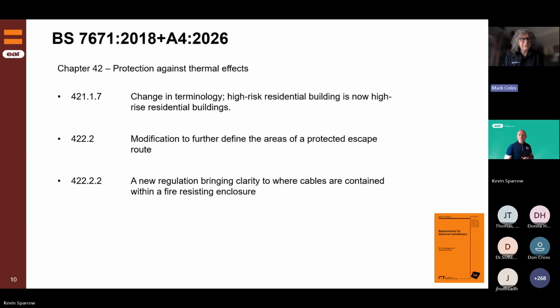Into chapter 42, protection against thermal effects, 421.1.7, change in terminology: high risk residential building, HRRB, is now high rise residential building. This is something that's gone on external to BS 7671. Essentially, since the Grenfell fire, there's been a lot of focus on that style of building, cladding, what are the risks, discussions of buildings over a certain number of floors or a certain height. In the discussions elsewhere, that is now the categorization: HRRB is high-rise residential building, not high risk anymore.